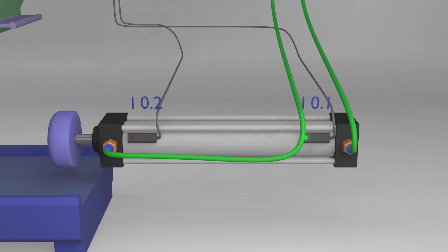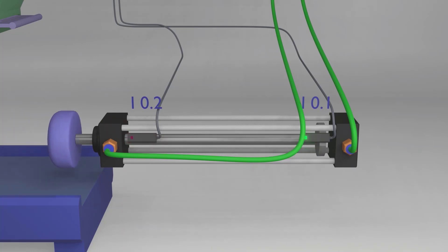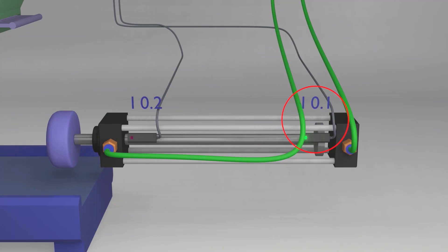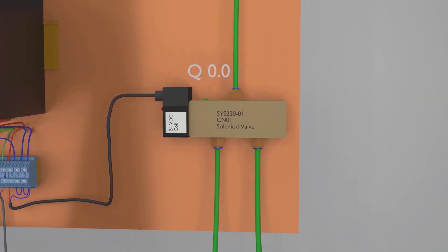Reed switches are used to detect the position of the piston. Whenever the piston comes in front of a reed switch, it detects the piston and sends a signal to the PLC. When the piston reaches the front end, the front end reed switch sends a signal to I0.2. When the piston comes back, the back end reed switch sends a signal to I0.1.